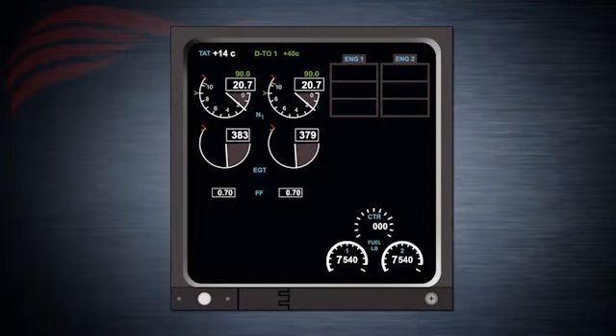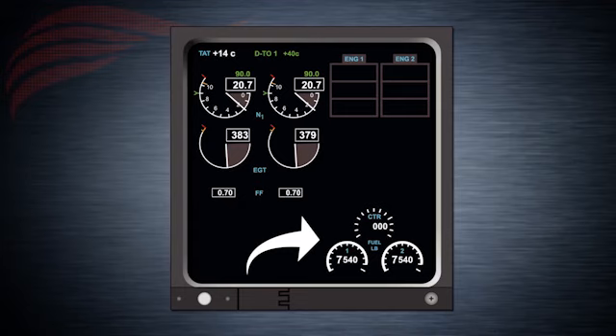A low warning will be displayed on either main tank's gauge when its quantity depletes to either 1,000 or 2,000 pounds as selected by the customer. The tank must, however, meet this condition for 30 seconds before the warning is triggered. The warning will disappear when tank contents rise to 2,500 pounds if the 2,000-pound trigger criterion has been chosen, or 1,250 pounds if the 1,000-pound condition is set up.